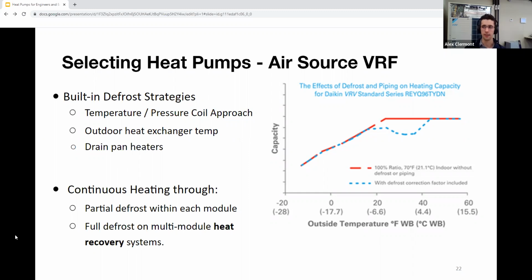The blue dotted line actually shows the corrected heating capacity based on defrost, which will occur on the outdoor unit if it's doing heating in our climate. And you can see that capacity gets affected because of the defrost. When the unit's in defrost, its outdoor coil is going to get full of ice and snow, and water will freeze on the outdoor coil. That's not very good for the air source machine because it makes it difficult to extract heat from the air.